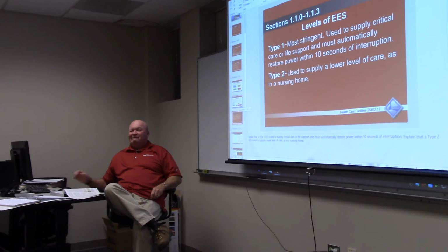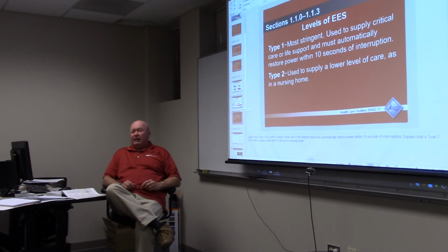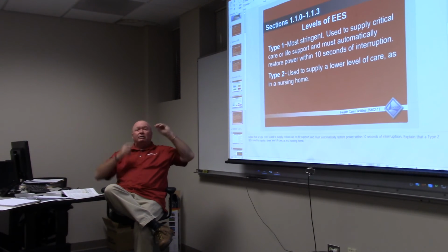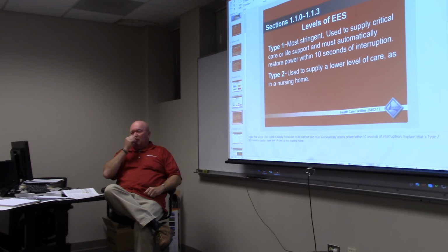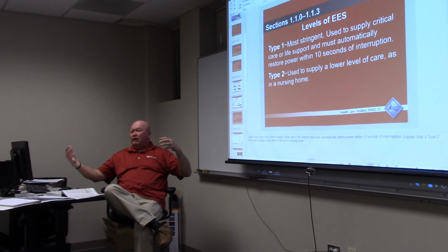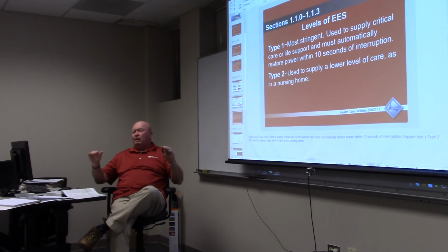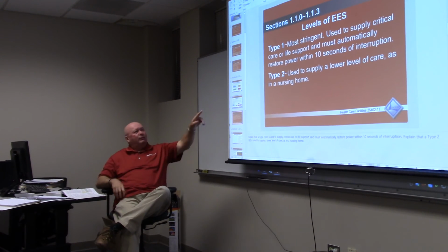What about UPSs and stuff? Like if you're operating on somebody, do they have an alternate source of power? Yes, the UPS, an uninterrupted power supply. But until we see something different, I think this is like minimum standards. In surgery we're going to have a UPS unit, but that's more specific, whereas this is just minimum standard type of things. You don't want any power to even blink, we don't want the lights to go out and the doctor standing there counting down seconds before they can operate again.